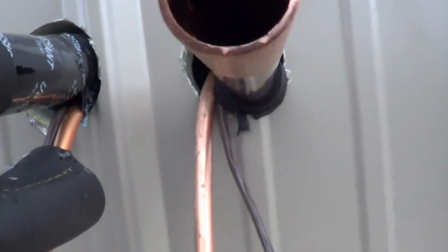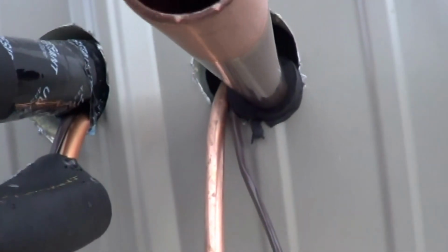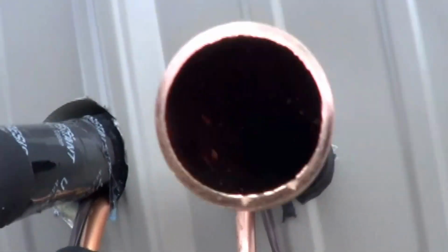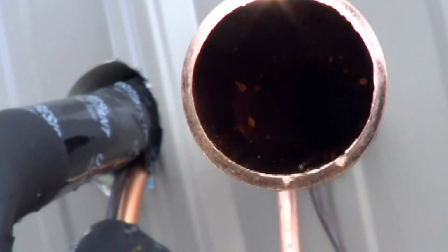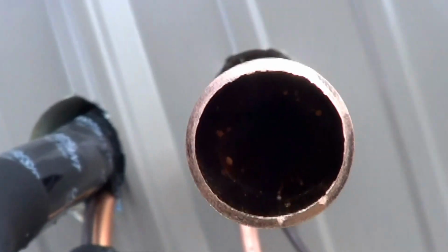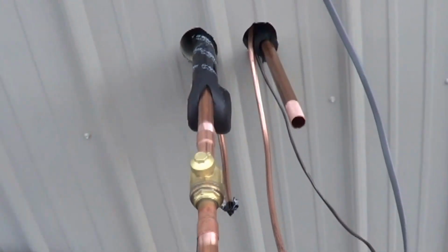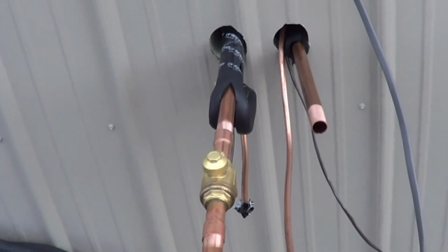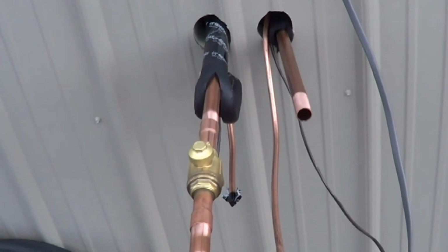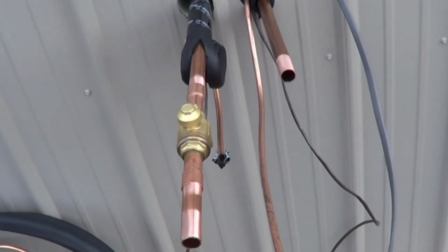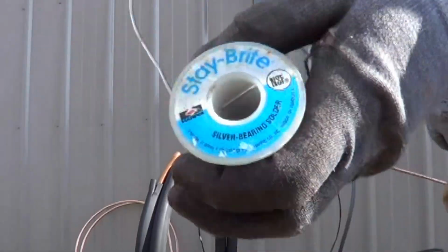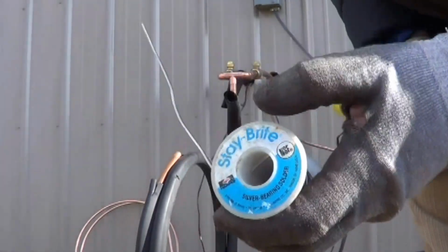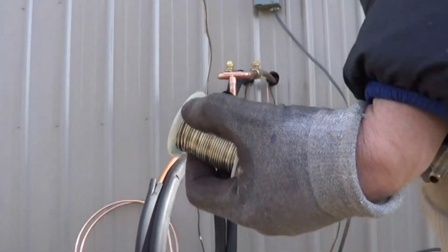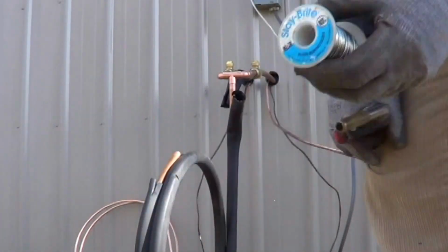You can see in here, significant amount of condensate got into the line. You can see that. Because the line was cold outside and is drawing in moisture and condensating. So I'll have to do a good triple evacuation on this one, get all that moisture out. 5% silver solder, low temperature. It's called Stay-Brite.